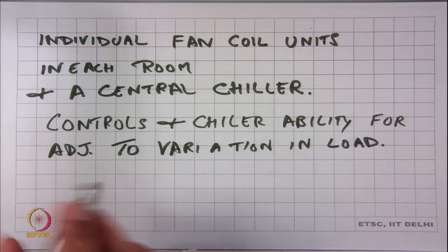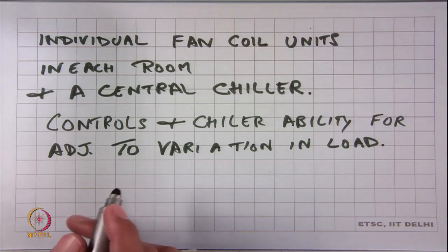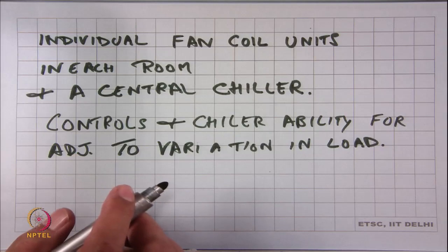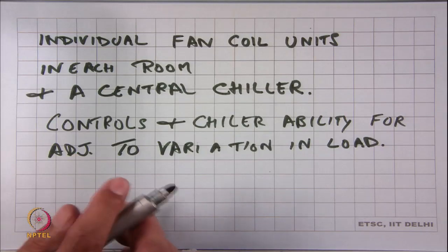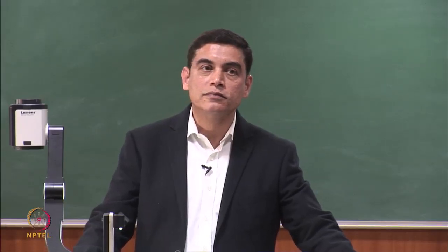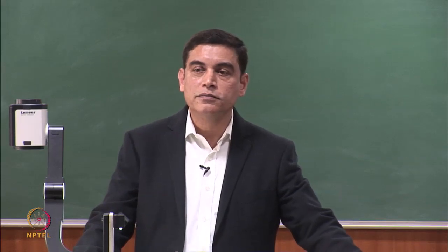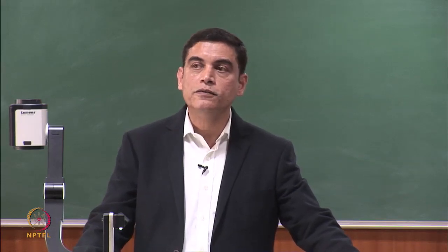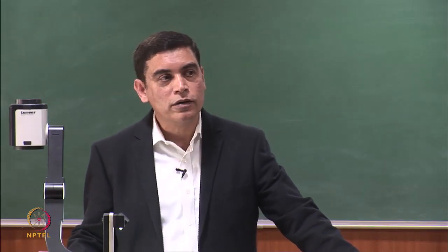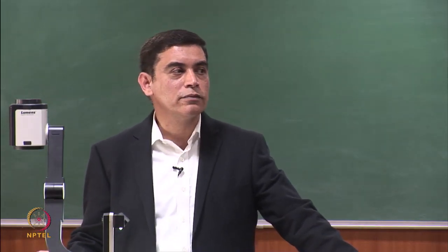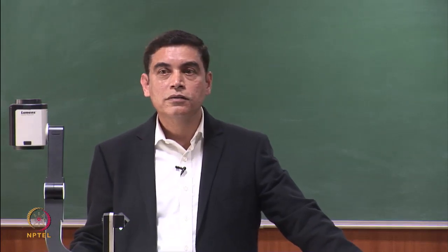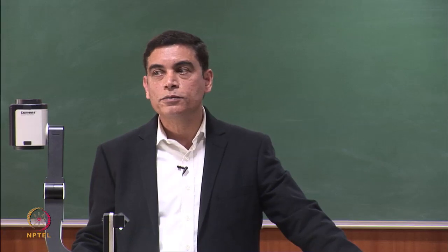Another solution would be VRV systems with indoor units and a common refrigerant circuit. I would stay away from that simply because of issues related to breakdowns — given that it is not such a controlled facility, potential damage to piping could leave the entire hostel with no air conditioning. But as an option it is also valid.